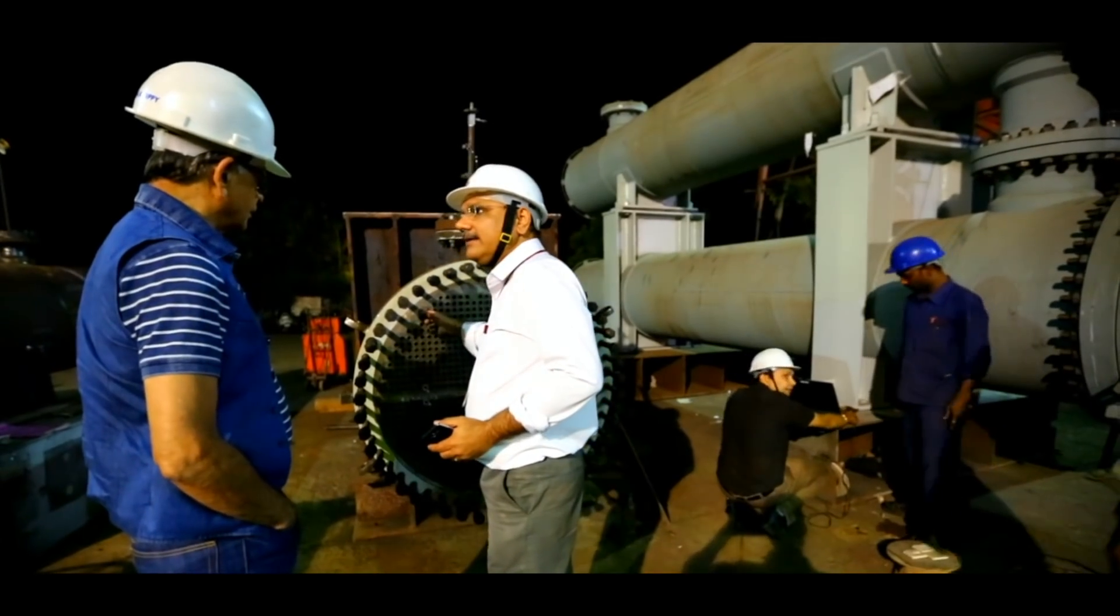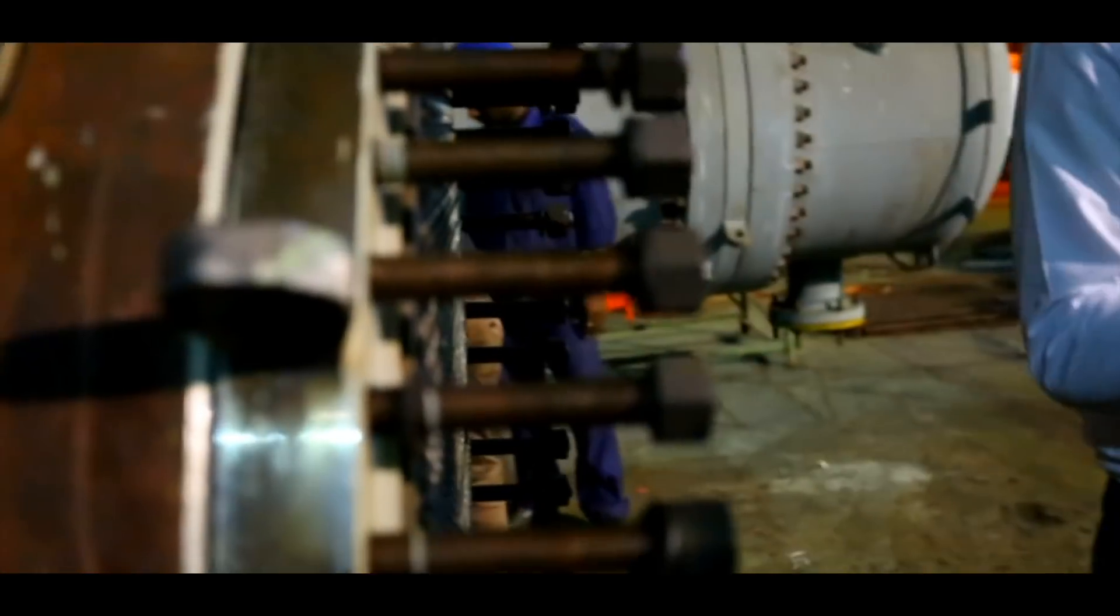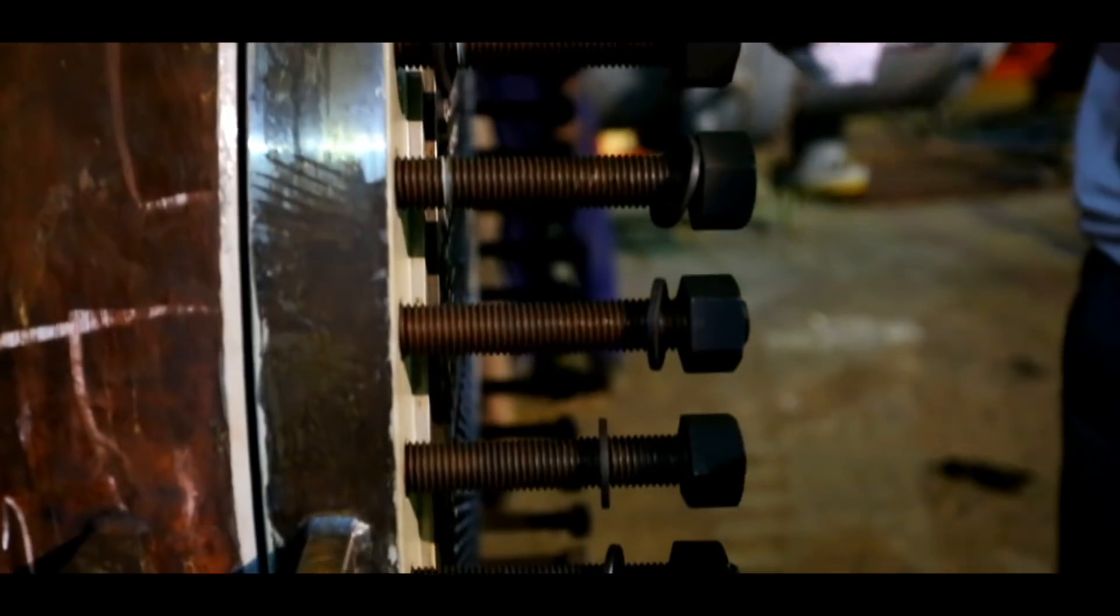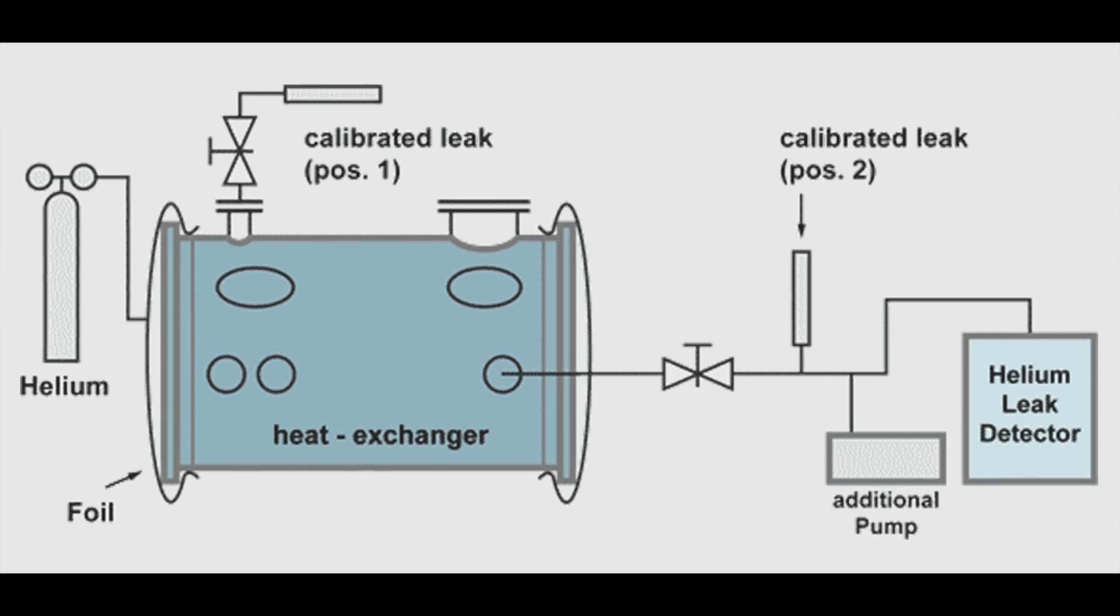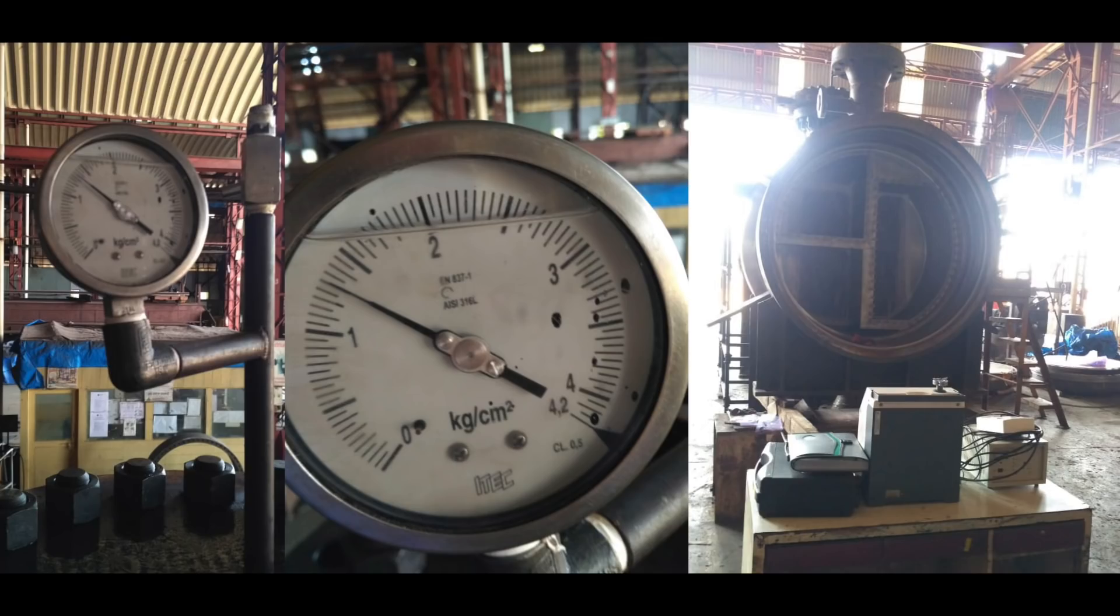Point 6: To ensure equal compression of the gasket under each bolt, the linear measurements of the compressed amount can be measured in a number of ways. Point 7: A helium test is conducted at the design pressure to ensure 100% leak-proof joints.